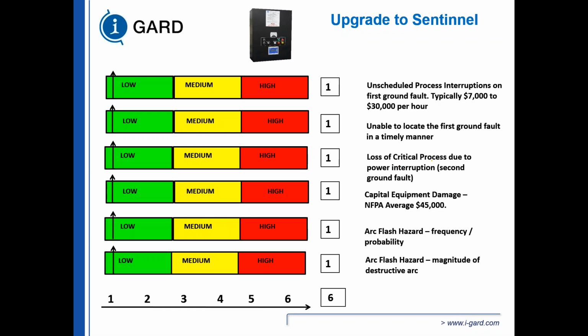Loss of critical process due to power interruption, 1. Capital expenditure, 1. Capital damage, actually, there's no damage. In fact, once you employ a resistance grounded system, you have less damage at the point of the fault because you have non-destructive current. Arc flash hazard frequency is very low, probability of that, due to NFPA 70E and Z462.